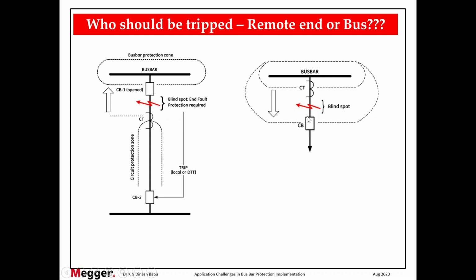So now what we do: after opening the breaker, the current in the CT will be monitored. Or you can even eliminate the CT from the differential. Once I eliminate it, the boundary is not there. The bus bar zone will extend up to here and it will trip. So in the first case, trip the remote end. And in the second case, trip the bus bar. So who should be tripped, remote end or bus bar? This is a common question. The answer is: it depends on your circuit. There is no final decision. It all depends on where your CT is located. It changes from single line diagram to single line diagram.